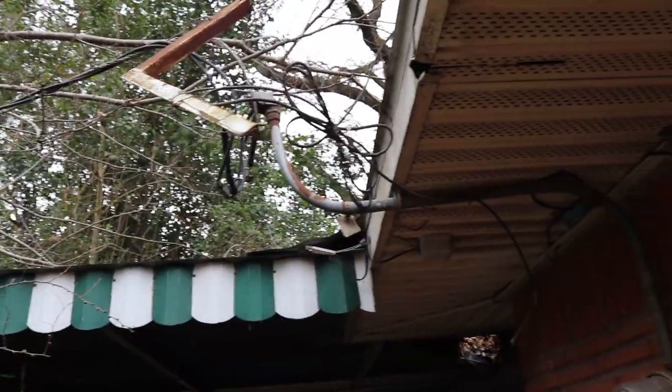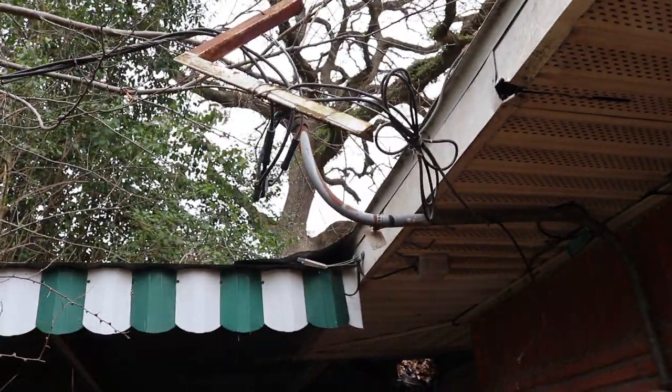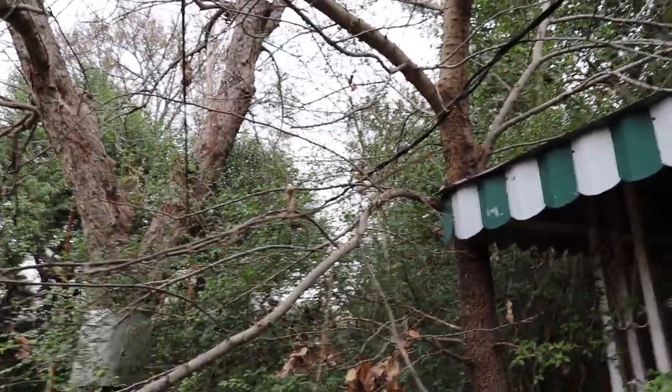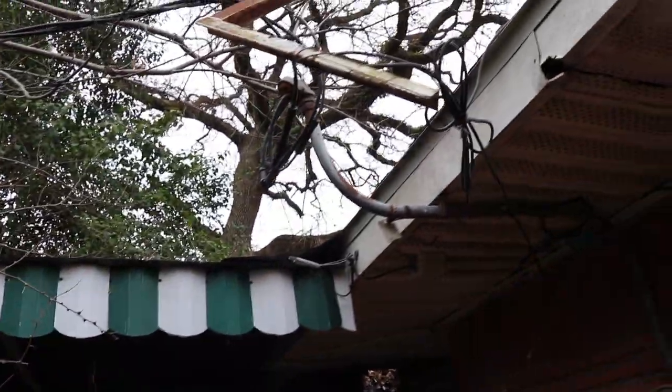One of the final things is the service mast — it's tangled up, it's not high enough, and it's going through trees. This is something you definitely want to take care of, because you'll lose power to the property and it's not safe.